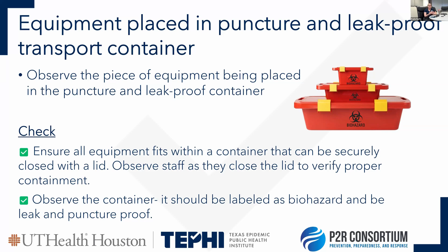Before they close the lid, so they put the piece of equipment in the container, they should be spraying it down with an enzymatic spray. And this should remain wet until it gets into the area where they're conducting a high-level disinfection. And the reason why it needs to remain wet is that this prevents biofilm forming.